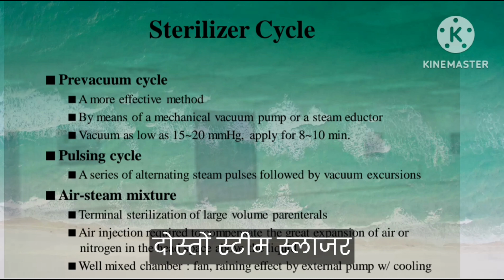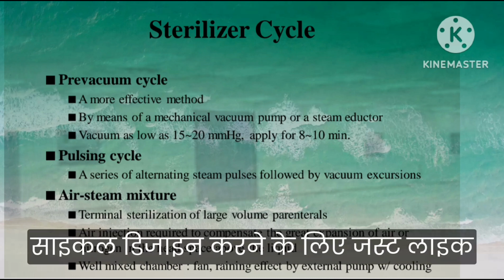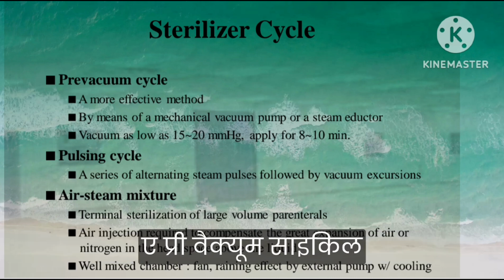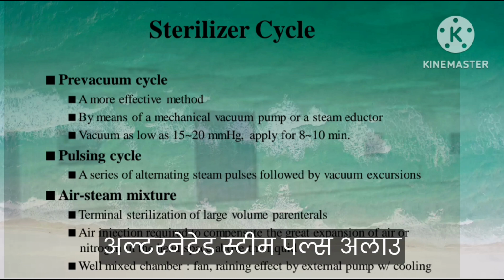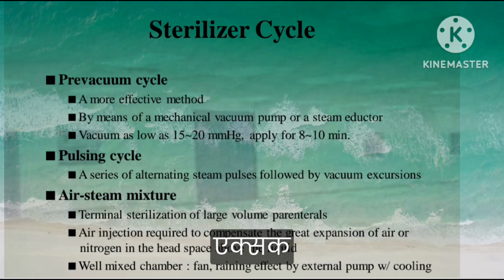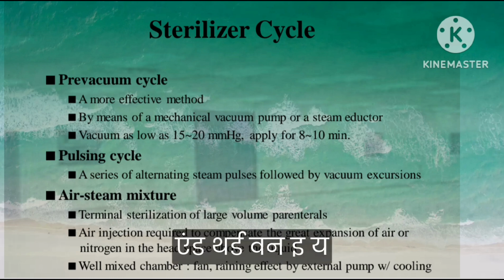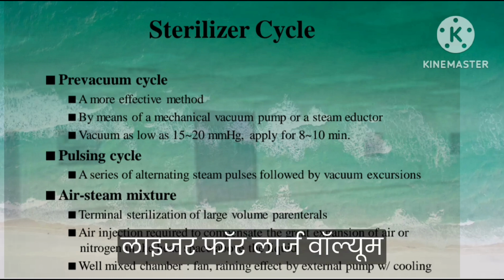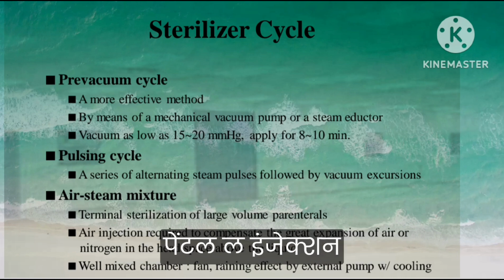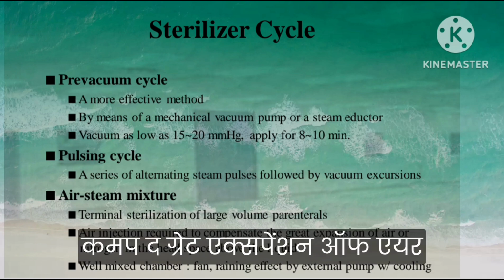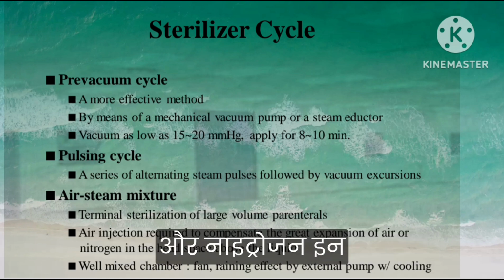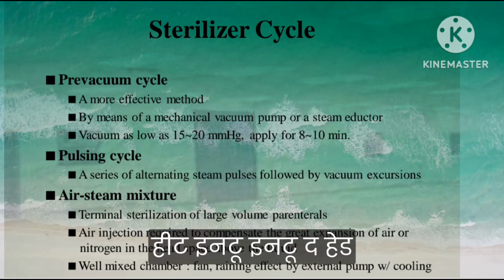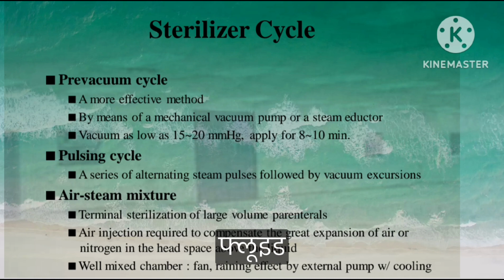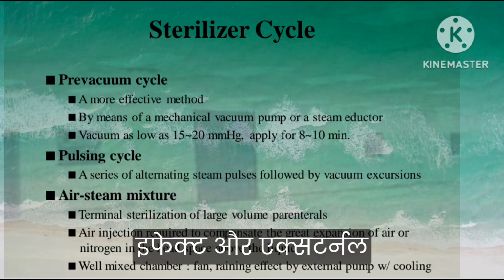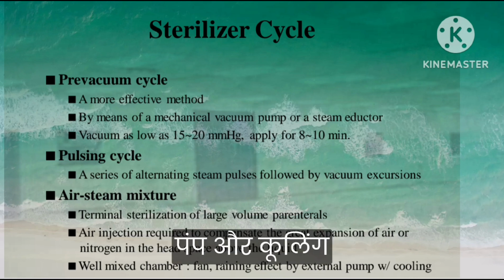दोस्तों, स्टीम स्टेरलाइजर में साइकिल डिजाइन करने के लिए डिफरेंट अप्रोच रहते हैं, जस्ट लाइक ए प्री वैक्यूम साइकिल. Pulsing cycle: a series of alternating steam pulses followed by vacuum excursions. And the third one is an air steam mixture, a terminal sterilizer for large volume parenterals. Air injection is required to compensate for the great expansion of air or nitrogen in the heat in the head space over the fluid. Well mixing chamber, fan, raining effect or external pump for cooling. Cycle development.